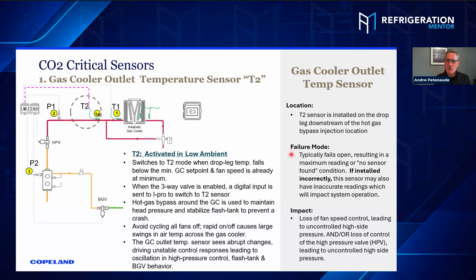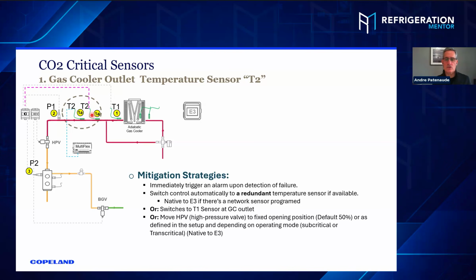But similar thing, right? If you lose that sensor, you get loss of fan speed, leading to uncontrolled high pressure, because now this sensor is doing the exact same thing as T1. It's just that it's in a different position. So same mitigation, similar mitigation strategies. If it fails, you can actually trigger an alarm, switch to the redundant sensor. Or in this case, if you don't have a redundant sensor, you can switch back to T1. Now, T1 is going to miss this hot gas flow, but again, it can limp along until you get someone in to fix it. Or, as soon as it warms up a bit, of course, you're going to be switching back to T1, but it's a limp along feature. Or you can switch to a predefined high pressure valve percent opening, again, to limp along. So there's some strategies there.